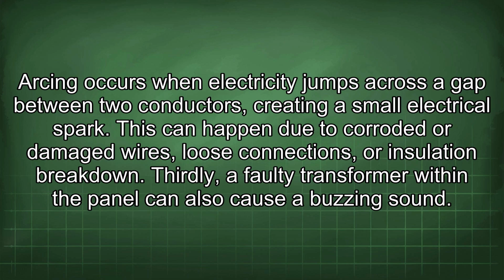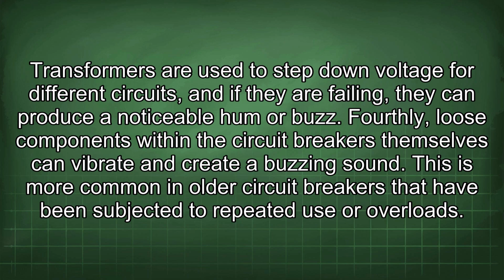Thirdly, a faulty transformer within the panel can also cause a buzzing sound. Transformers are used to step down voltage for different circuits, and if they are failing, they can produce a noticeable hum or buzz. Fourthly, loose components within the circuit breakers themselves can vibrate and create a buzzing sound. This is more common in older circuit breakers that have been subjected to repeated use or overloads.